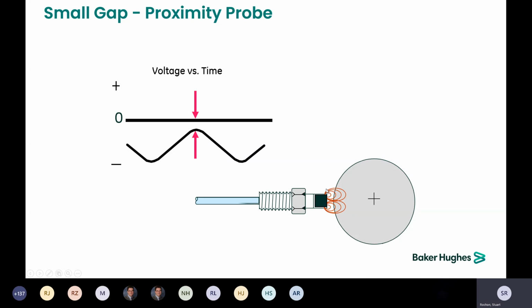There is a dead band of about 10 thousandths of an inch from the probe tip before it starts to change. So generally you have to get about 10 thousandths away from that probe tip before you start seeing the voltage go more negative from that 0.65 volts.